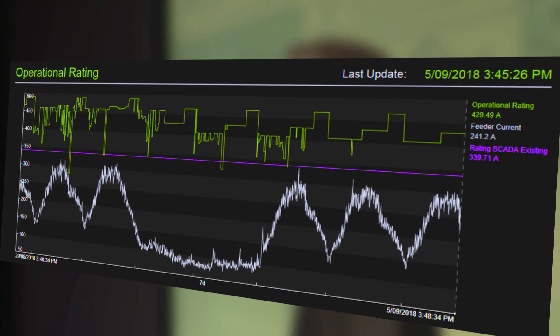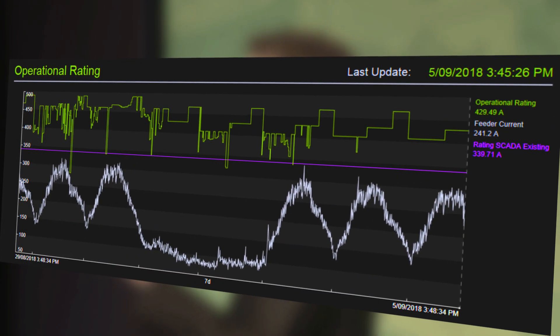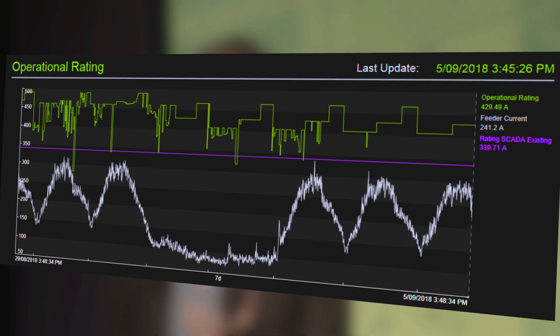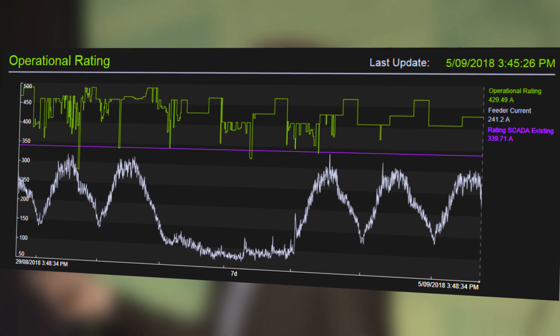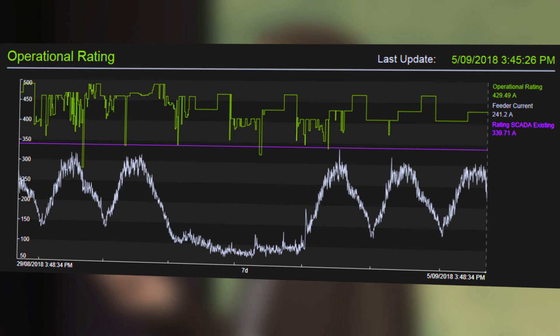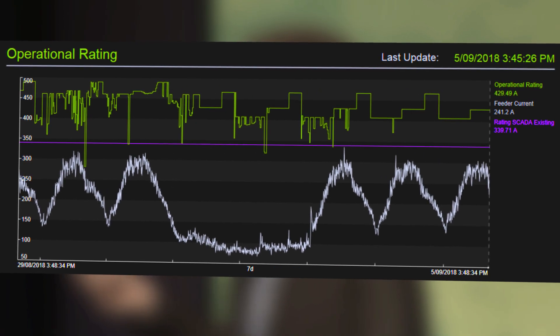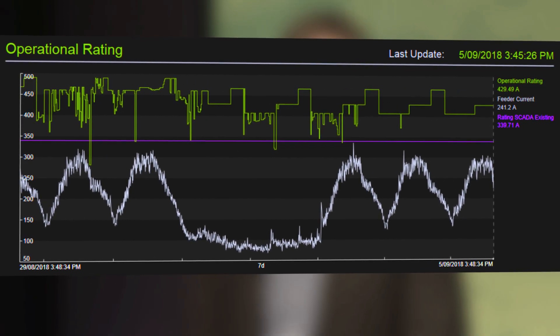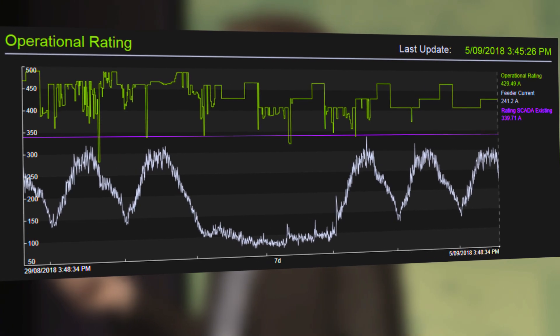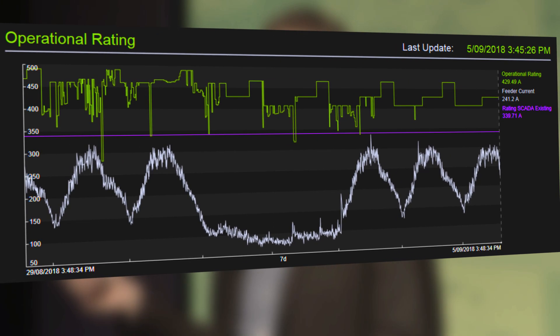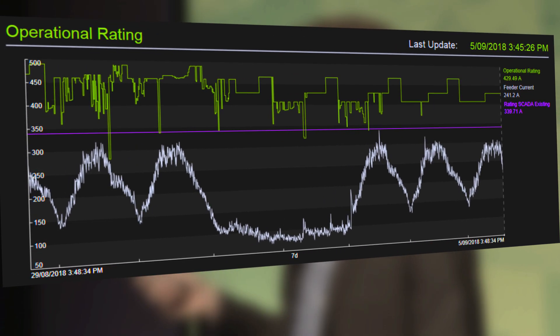Here on the bottom in white, we've got the actual load on that feeder, read through SCADA. Purple is the existing static rating. And then the green — the beautiful green — is the result of our calculations. For the majority of the time, it's quite a lot higher than the purple. In fact, there are points in this chart where it's 44% higher than the static rating.